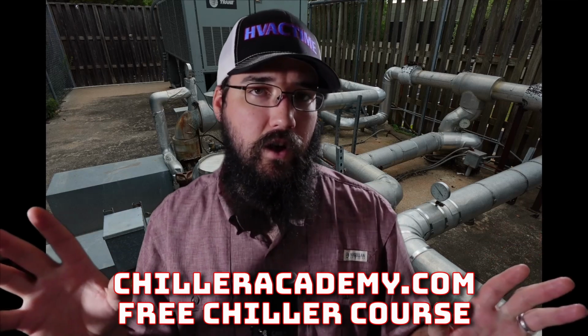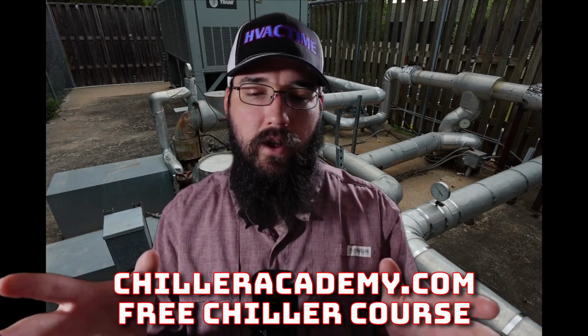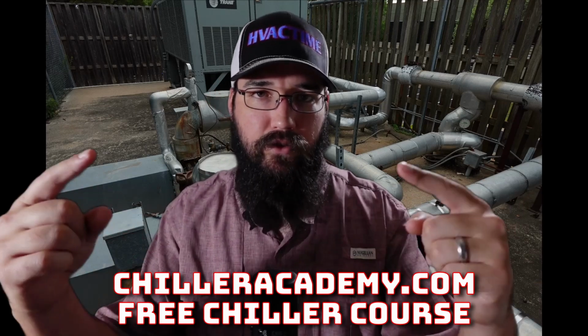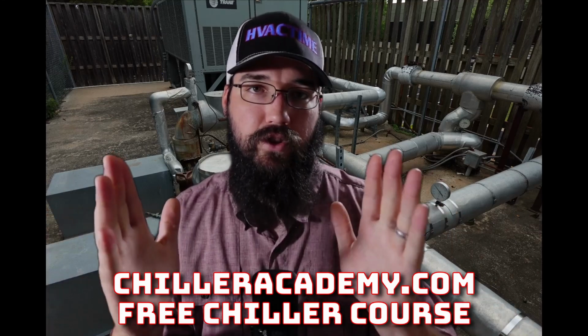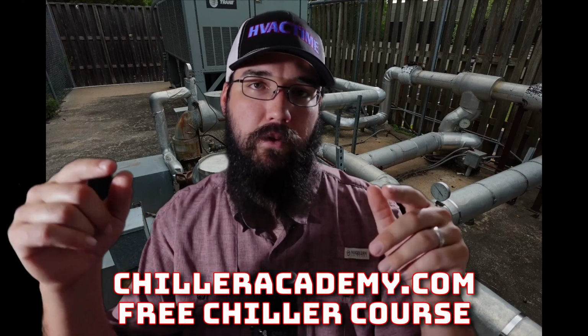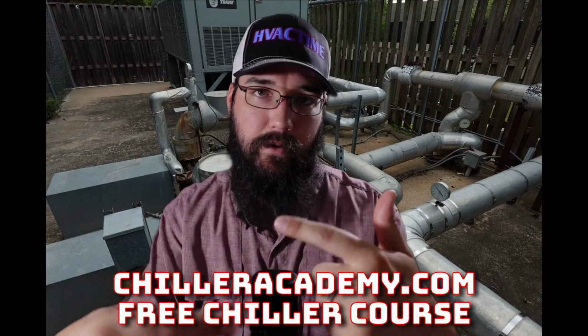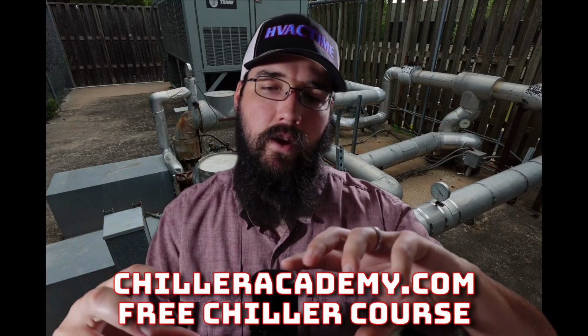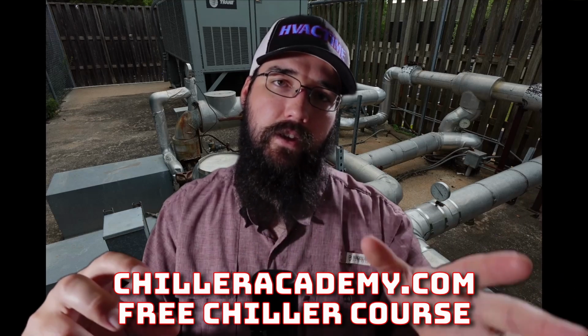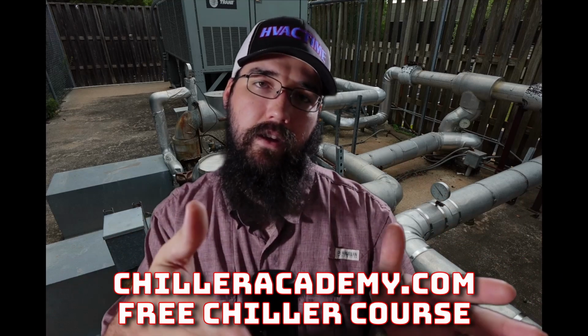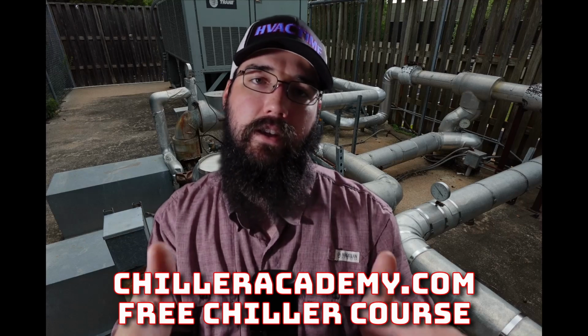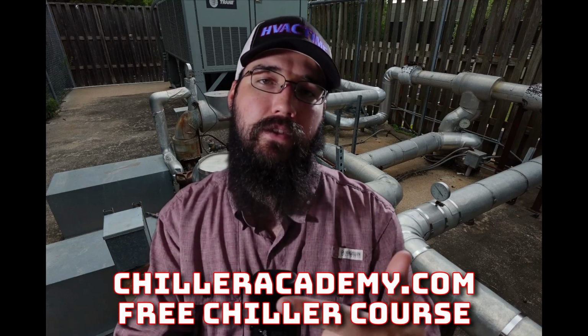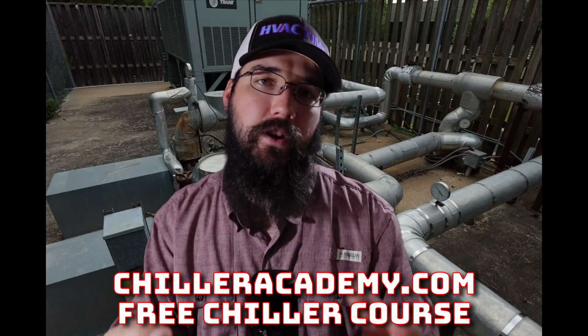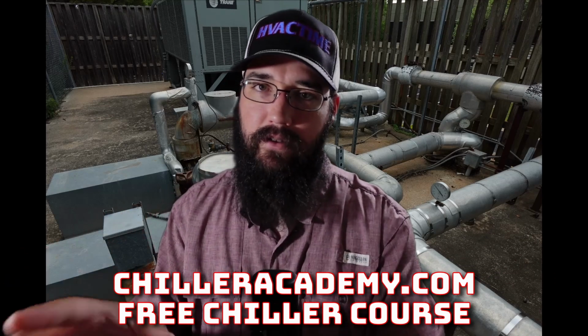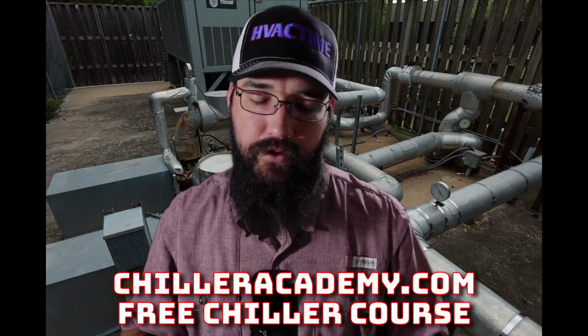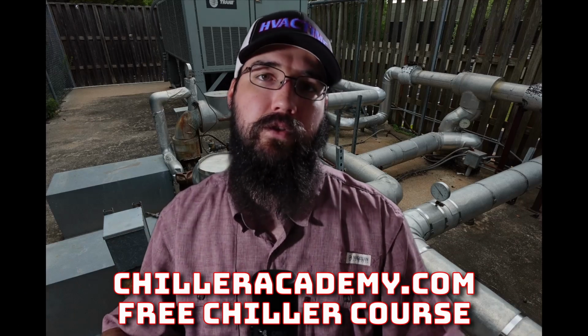And all of this is for non-sealed bearings. So if you're not familiar, a sealed bearing has sealed shields. So the shields are the plates that go in between the outer and inner race, the rings that the bearings spin inside of. Those are your races. And the shield is the piece of thin metal that is hiding the bearing to where you can't see it. Now, if it's sealed, that means that it has a very special grease by the manufacturer inside of it, and that grease is going to stay there. That motor should not be greased, and don't play with those shields.